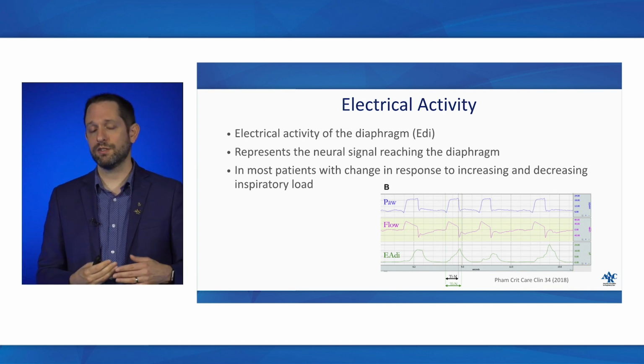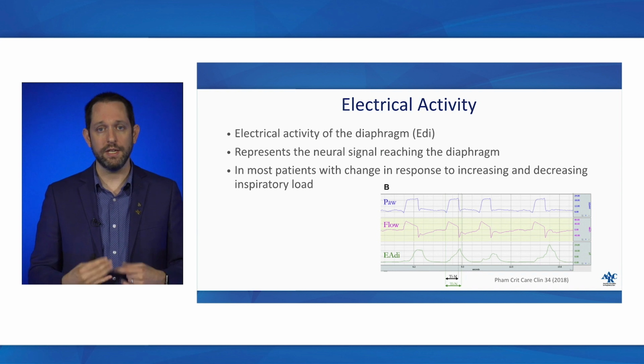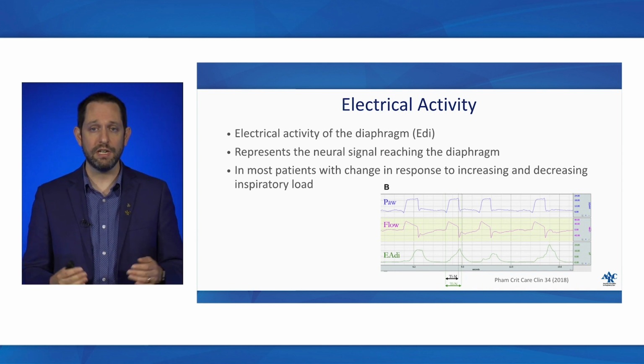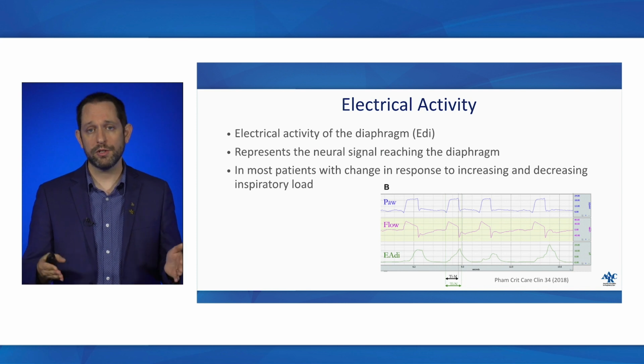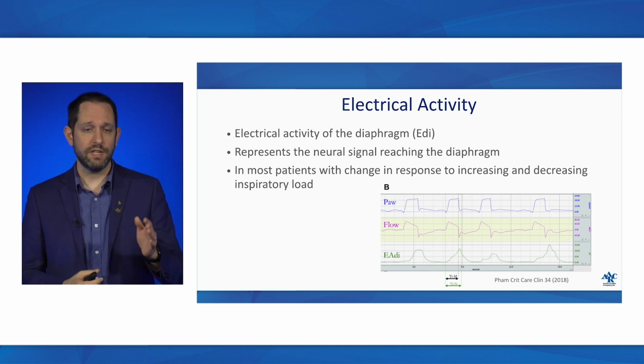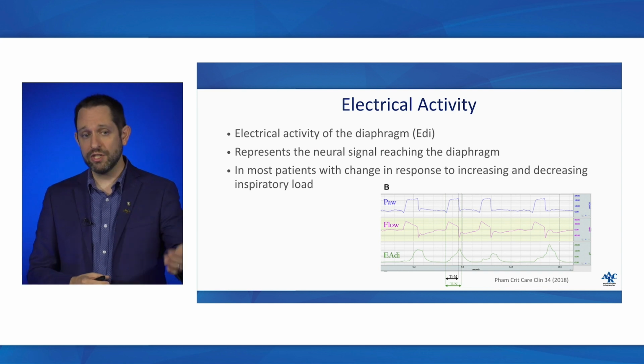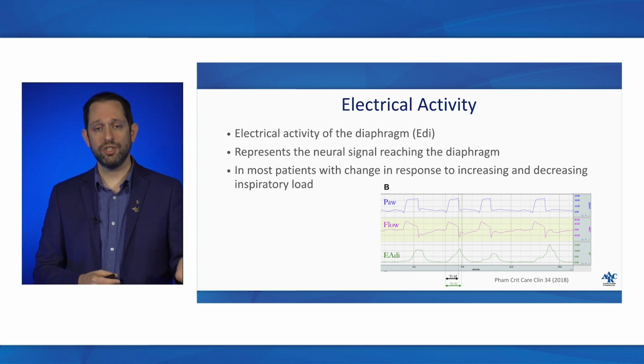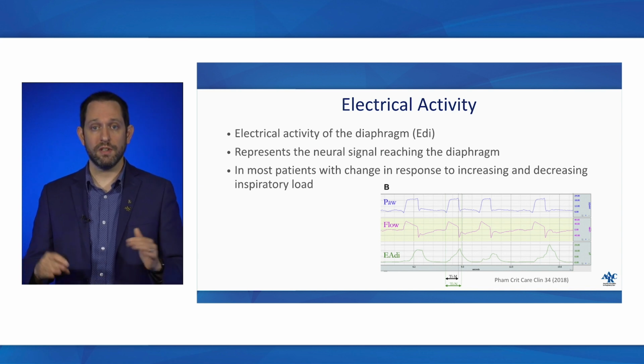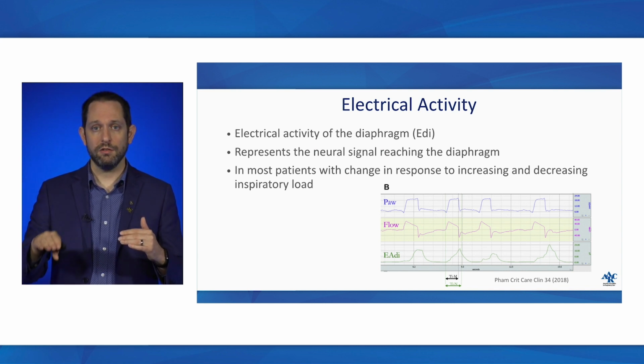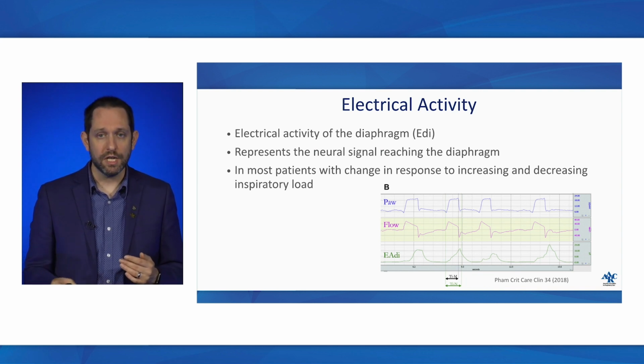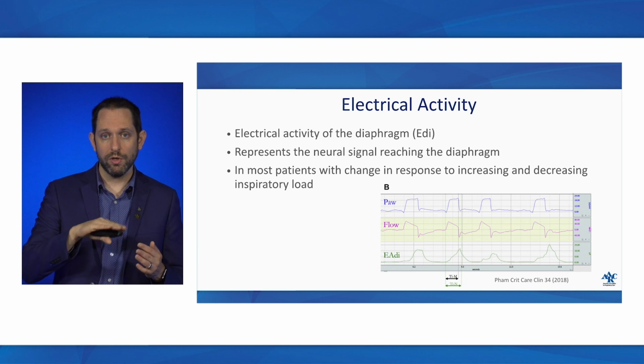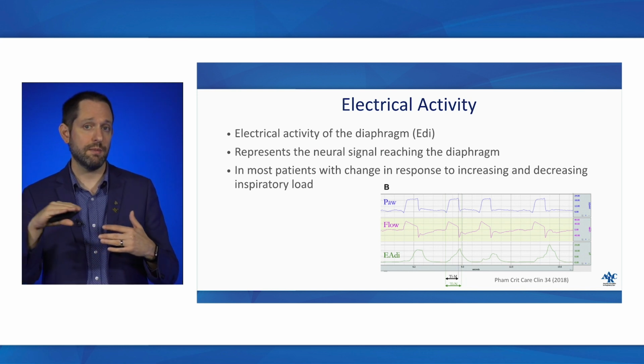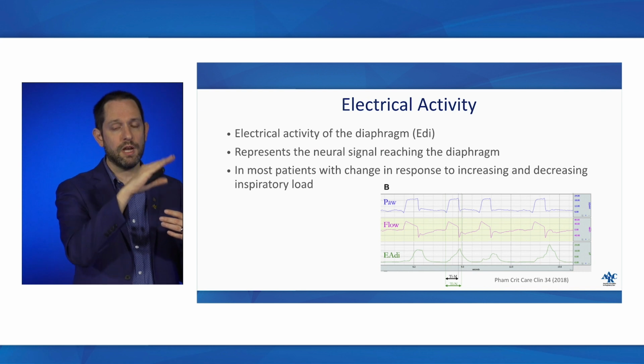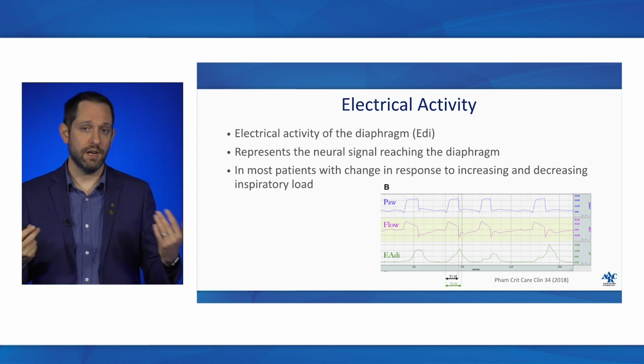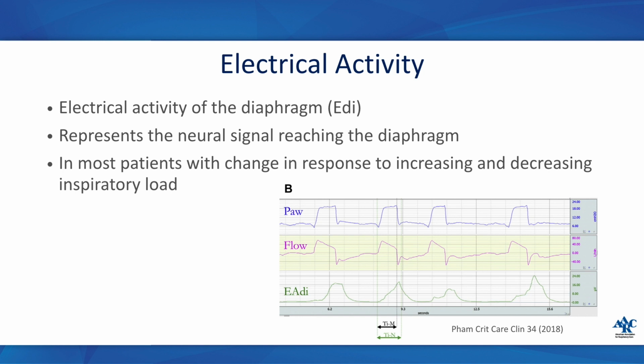Having said that, EDI is also a very, very useful tool for monitoring inspiratory effort in your patients and ventilator asynchrony. Even if you don't want to use the NAVA mode, you could monitor how well they synchronize with any mode at all. So it takes the electrical activity, it does represent the neural signal reaching the diaphragm from the brain, and in most patients, in response to increasing and decreasing inspiratory load, your EDI signal correlates with that effort. So if you increase support, the EDI should come down. If you decrease support, it should come up. If you're weaning the patient, you want to see that trend stabilize, or if it's continuing to rise, you know your patient's working harder and harder and harder, and again, it may lead to failure of your spontaneous breathing trial.